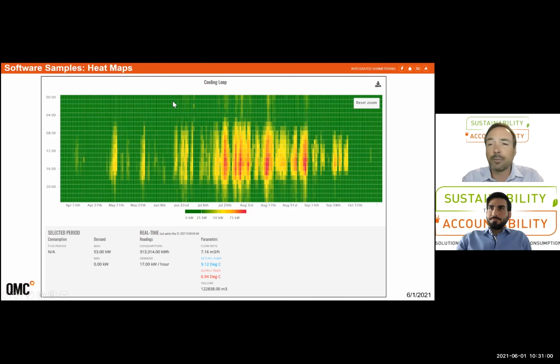And this is an example of a heat map, one of our favorite tools to utilize to have a quick snapshot of a load over a 1 month, 1 year period, what have you. This is showing hourly data for every day. Sometimes you can get down to 5 or 15 minute intervals, but you can obviously see the trends of this load very clearly shown when it's hitting its maximum energy use. And you can look for schedule offsets, evening and weekend offsets, and see any anomalies very quickly utilizing heat maps.